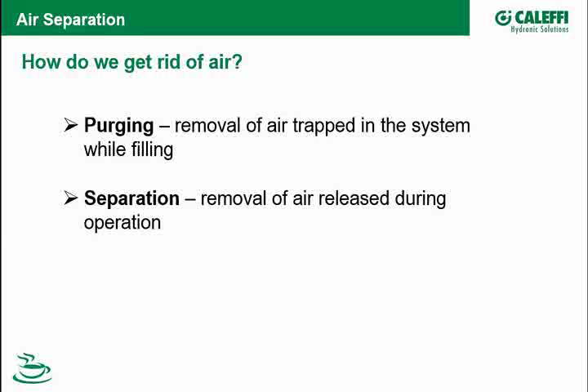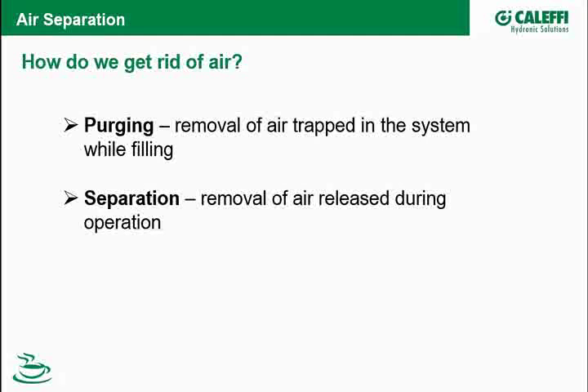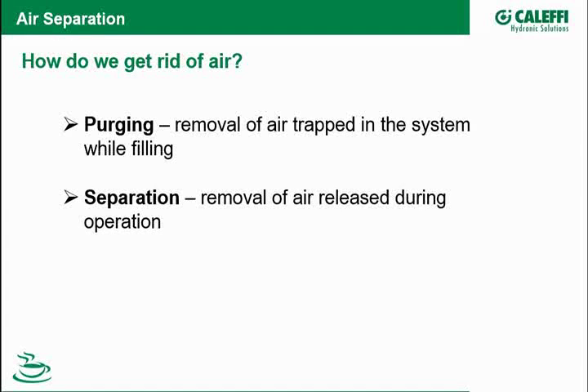Getting rid of air is really a two-stage process: it's about purging and it's about separation. Purging is getting rid of the air as you're filling the system up — I want to remove any trapped air pockets. In an ideal world when I start to separate, all I'm trying to do is work with the air that's in solution in the water of the system. If I don't do a good job purging, then during separation I also have to get rid of air that exists in standing pockets throughout the system.